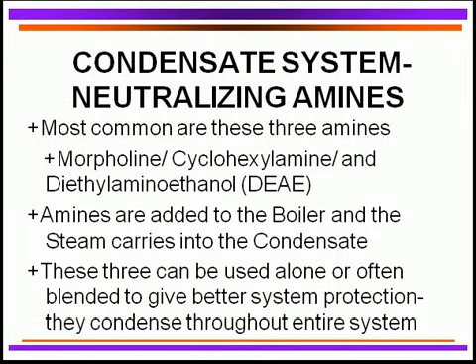We need to neutralize that carbon dioxide. The most common technique today is to use three different amines: morpholine, cyclohexylamine, and DEAE (diethylaminoethanol). These are excellent products that have been used for years, and they are often used together. The amines are added to the boiler, and the steam carries those amines over with the steam so they get into the condensate that way.